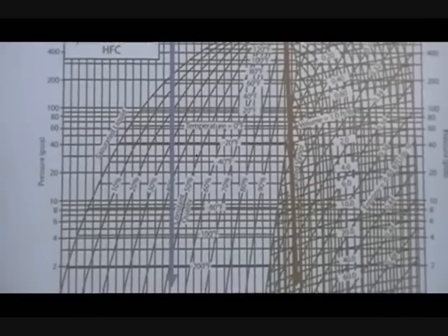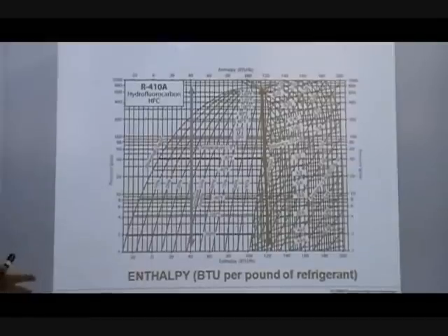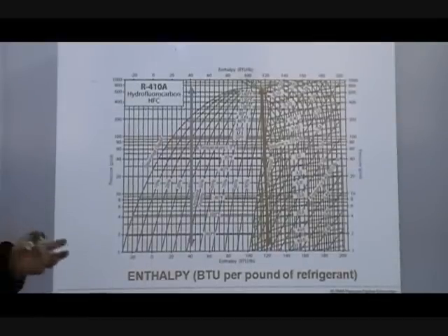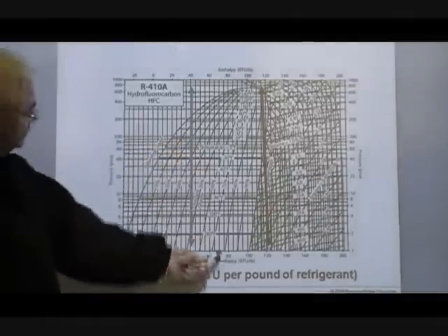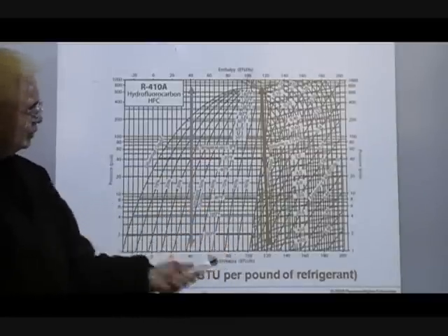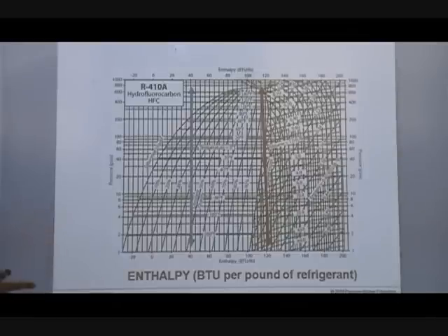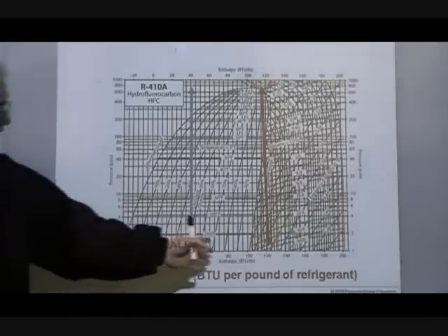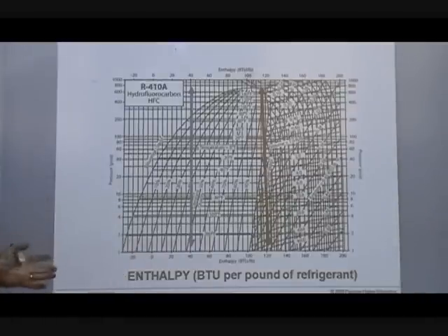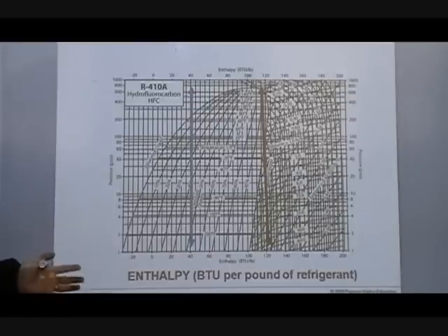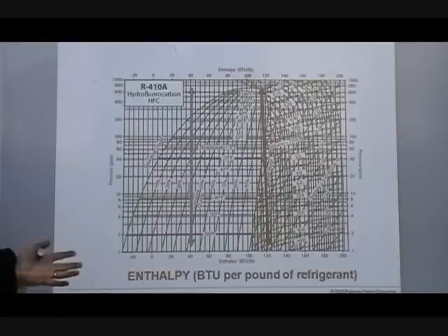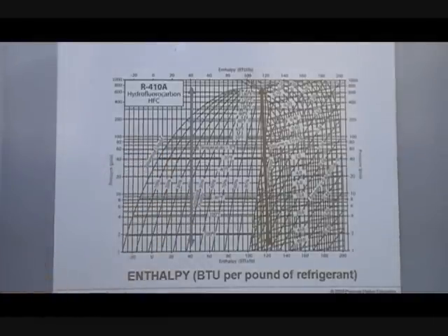If you've got a scenario where you know how many BTU you need — you remember that first calculation where you figured out how many BTUs are required to raise a certain amount of a substance so many degrees — when you know how many BTUs you're going to need, you can look at this pressure-enthalpy diagram and determine the capacity of the refrigeration system you need. You can determine how many BTUs per pound of refrigerant are going to be removed, and you might need a system with 6, 10, or 50 pounds of refrigerant. This is what the engineer uses to help design the system.